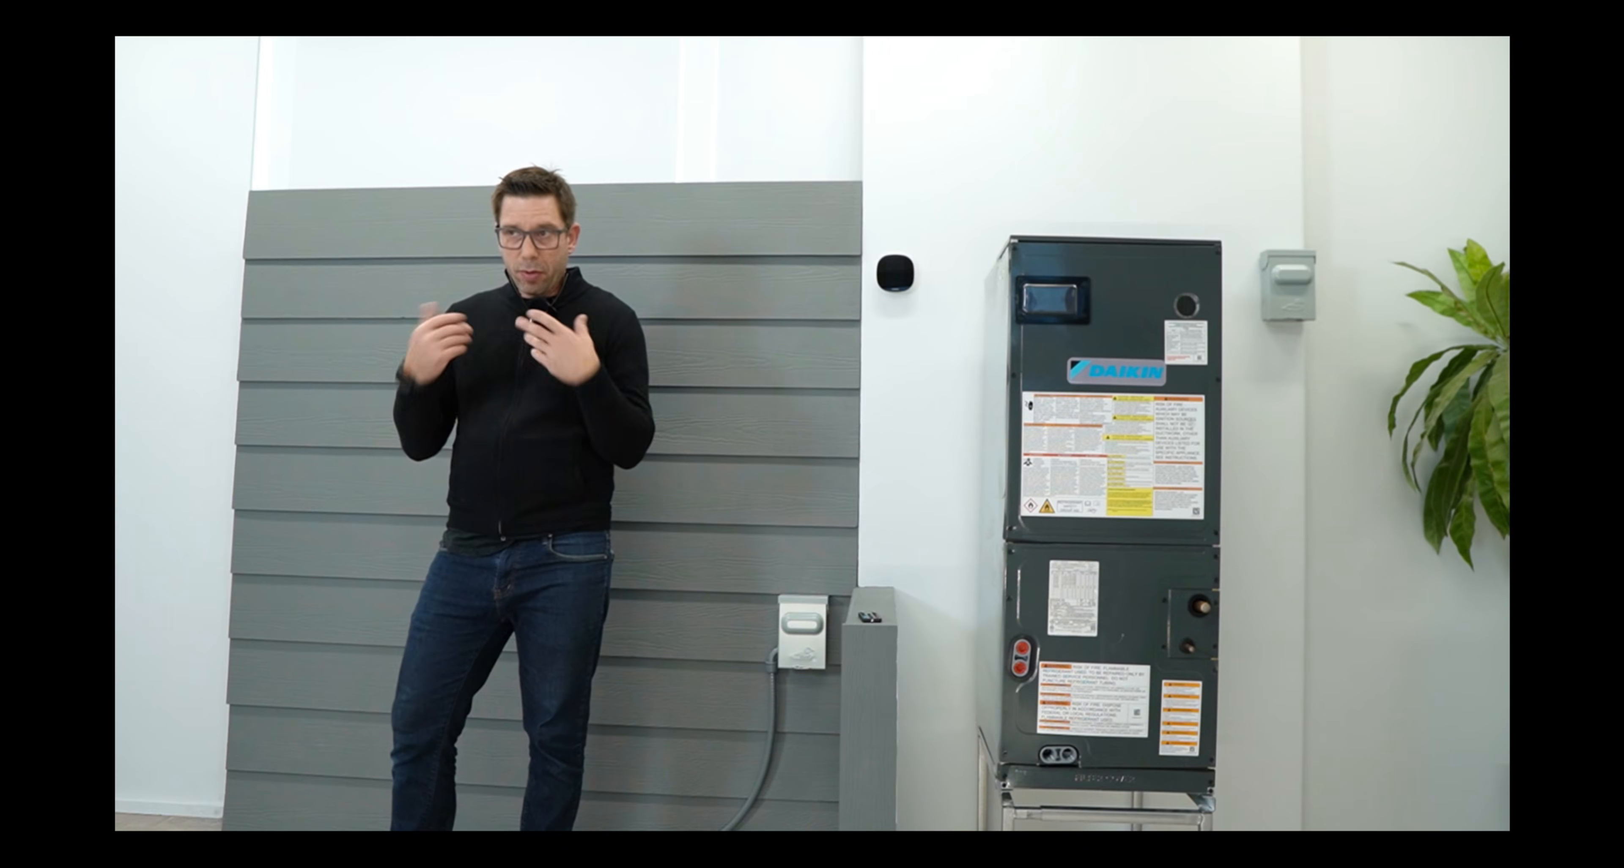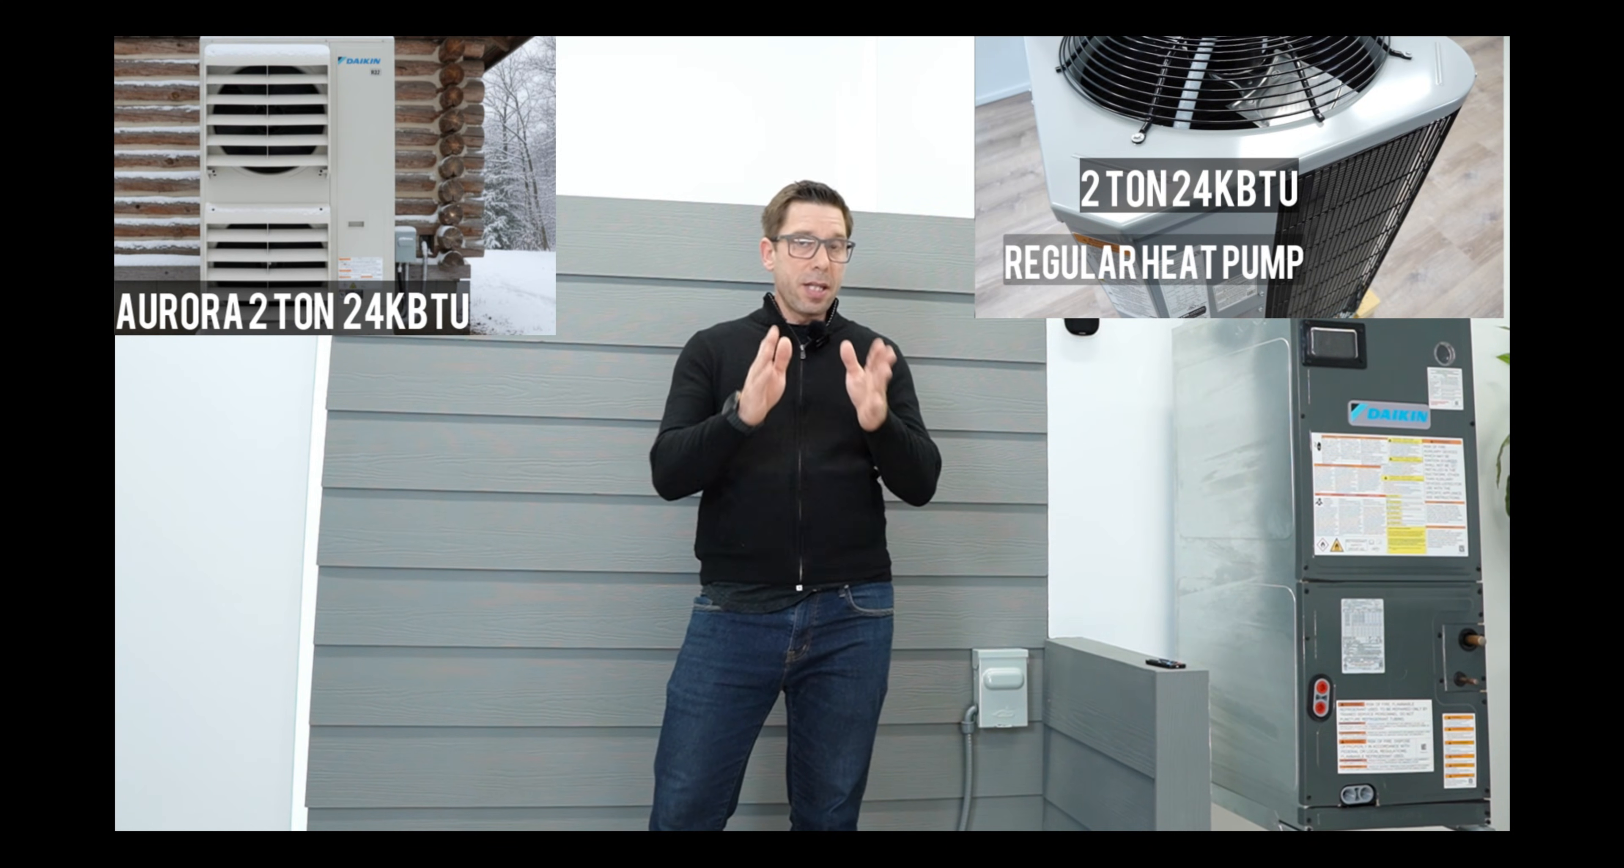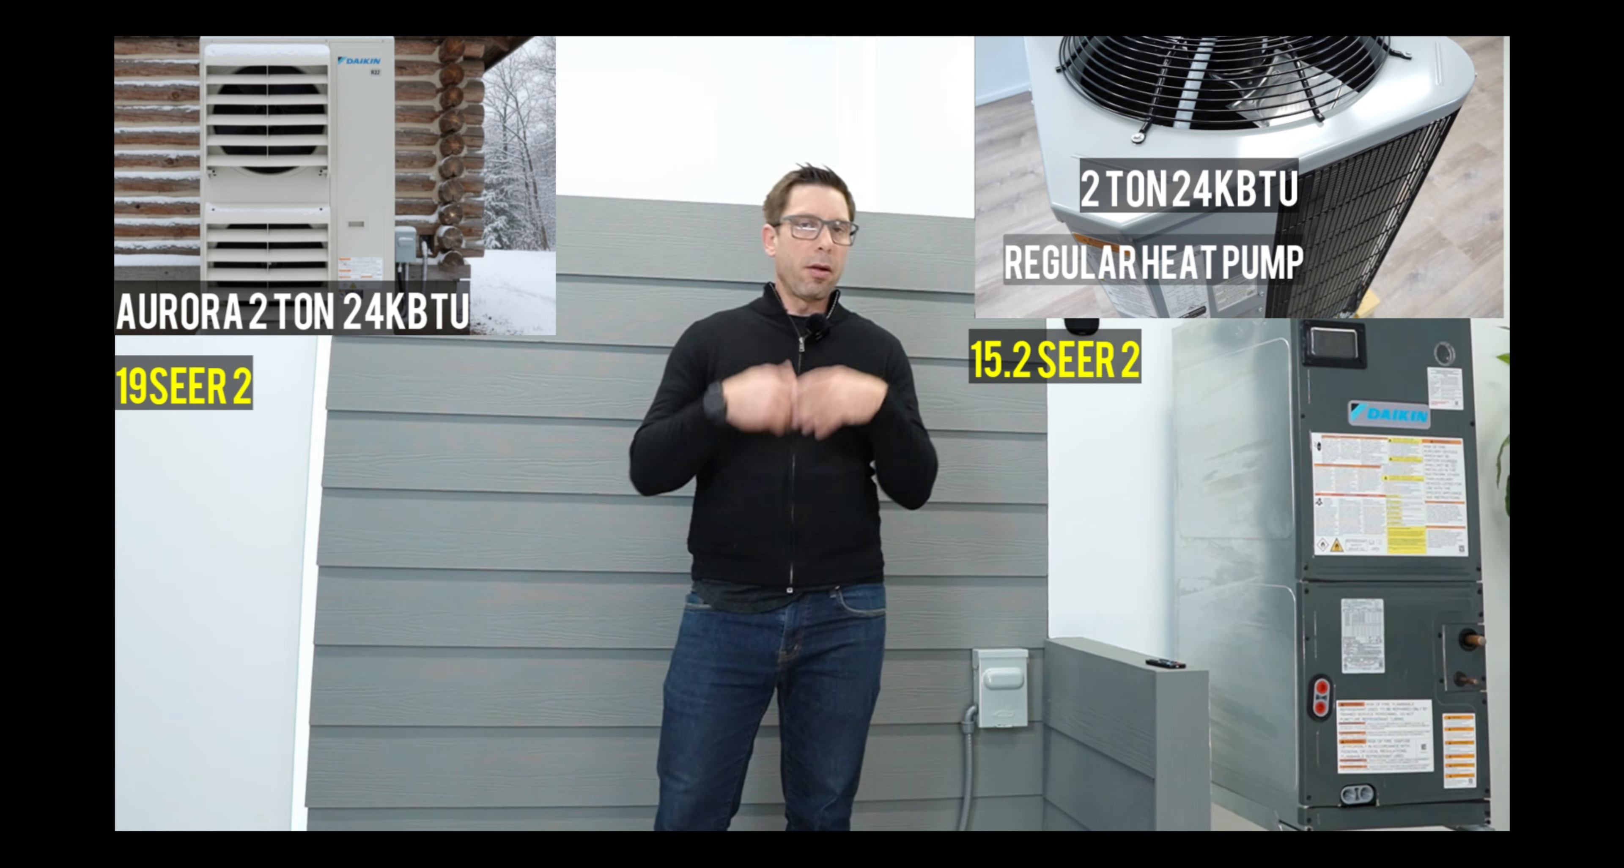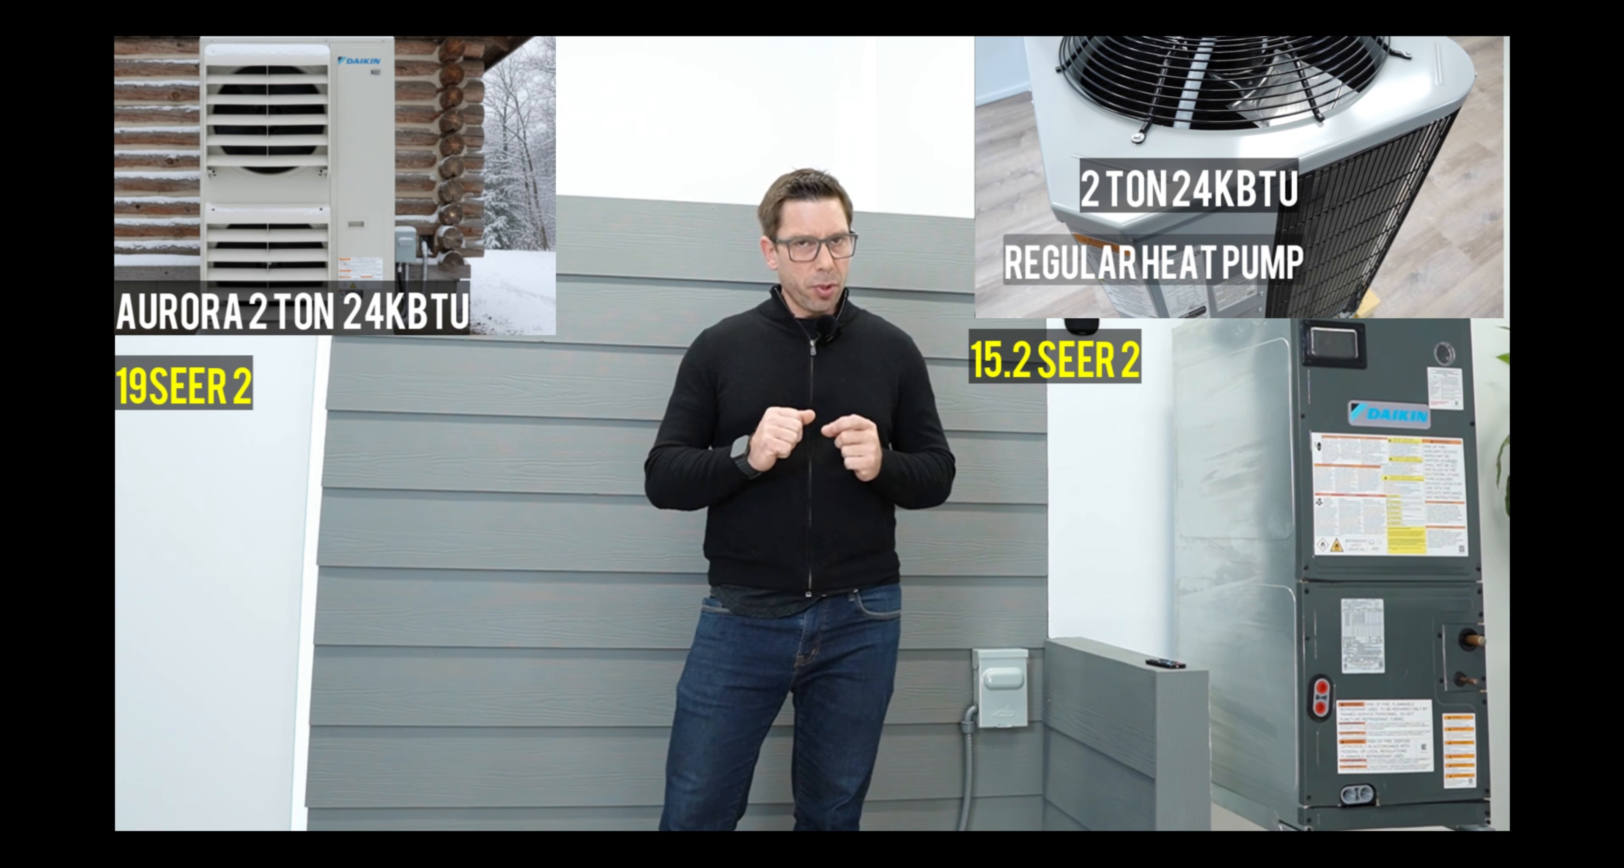Now, if you look at the components of a communicating cold climate heat pump versus a regular heat pump, even if you're a pro, you might have a hard time telling what the difference is. Let's take a look at how the system compares to a conventional heat pump. I have two systems here. Both systems have identical nominal tonnage. The Aurora is 19 SEER2, while the generic heat pump is 15.2 SEER2. The generic version is actually a very good heat pump, and I have nothing against it whatsoever. Remember that every ton is 12,000 BTUs, and a 2 ton unit is 24,000 BTUs.